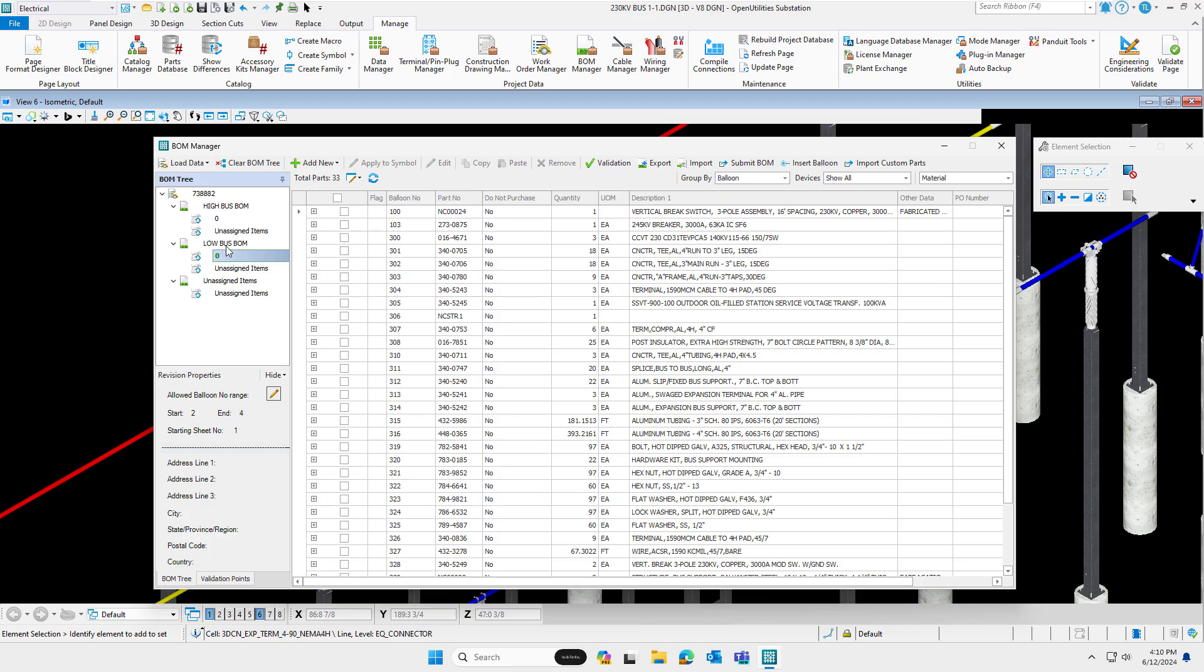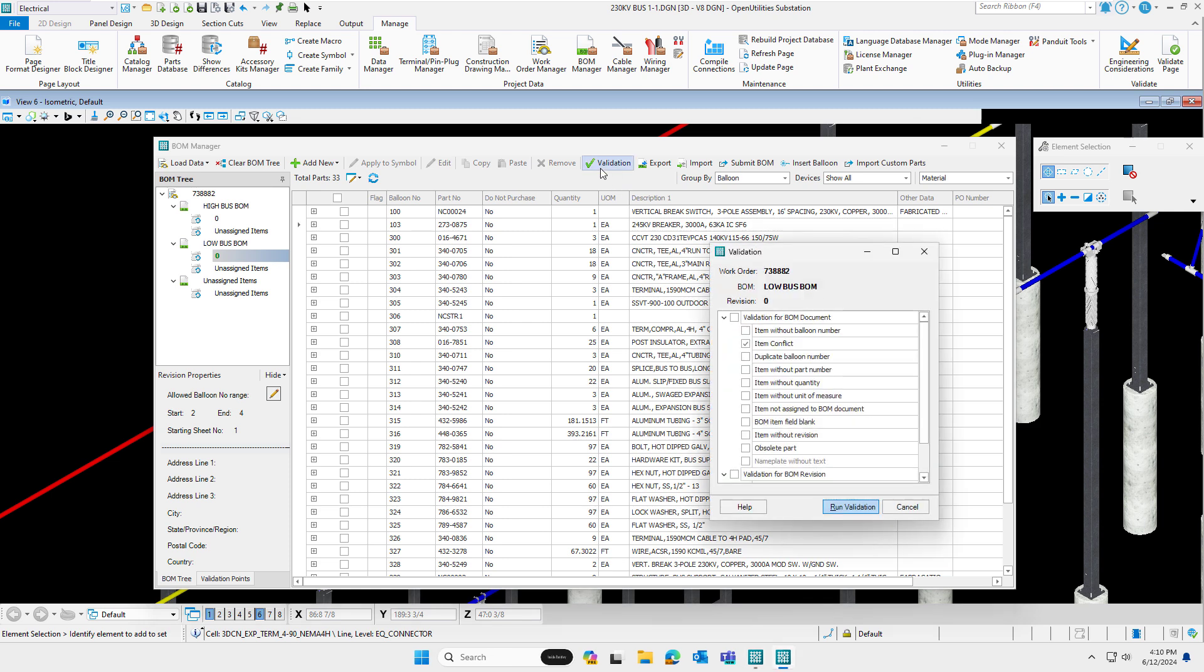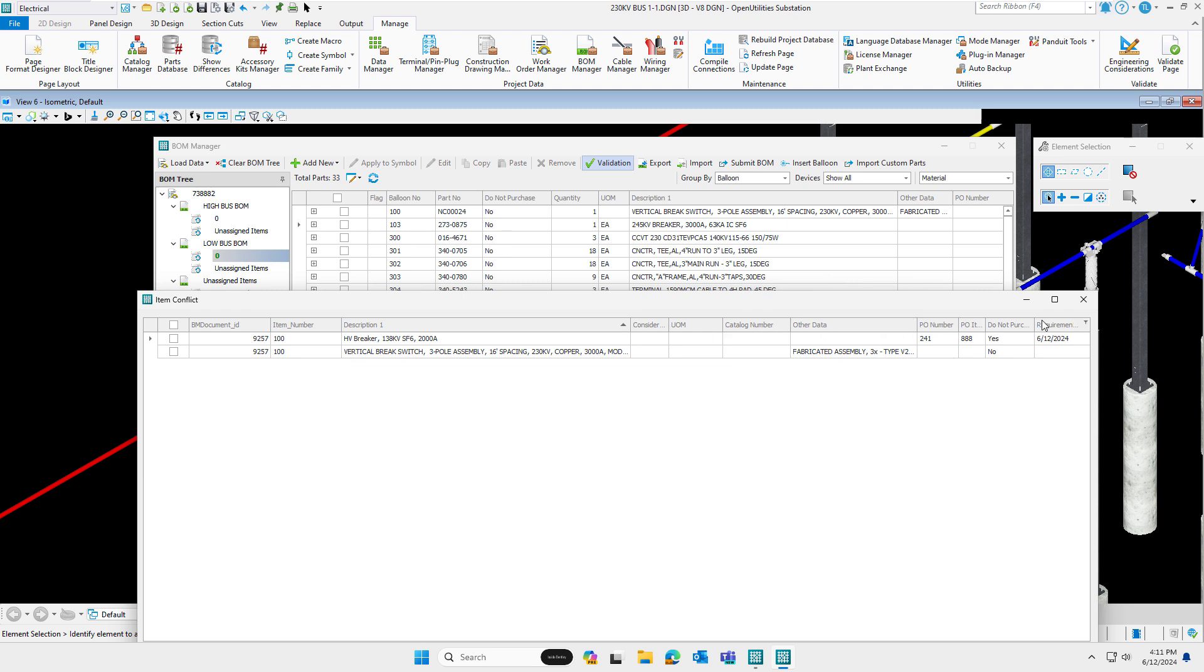Let's take a look at how this validation tool works. For example, on my low bus BOM, hone in and take a look at this first description here. You can see you've got what we call a non-coded part or a custom part. So this isn't a part from the parts database. I've typed in a description, in this case, a vertical break switch. I've purposely set up this condition for this demonstration. And I know in the back end that there's duplication there because I intentionally did that. However, if I just go in and select that validation, item conflict, you can see. I'll run that validation and this presents the issues. So it tells me item 100 for my low bus BOM. So I'm on this node, revision zero of my low bus BOM. Item 100, I have some duplication. One record says it's a breaker. The other says it's a vertical break switch. And you can see the differences in all of the Bill Material Data Manager fields.